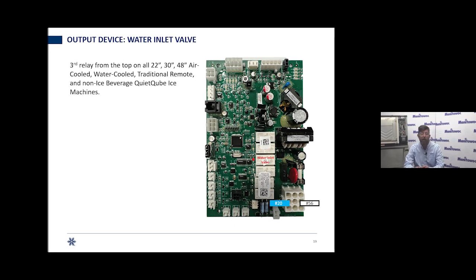All right, the water inlet valve. This is supposed to come on during pre-chill and then again during freeze to bust up any slush. But assume that you're not getting water. You verified that you do not have a water probe that's sensing, both by utilizing the input lights for the low and high water probe, or you have a working display and water low and water high both say they're not sensing. You could check across wire number 20, that blue wire, and wire 56, that white wire, and check for voltage. If you have line voltage and no water coming to that ice machine, well, you've got a working board. You have a probe that's not telling the board it already has water, so you need to go verify, do you have water coming to this ice machine?